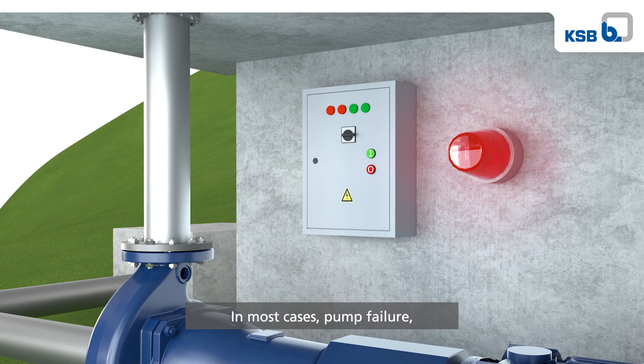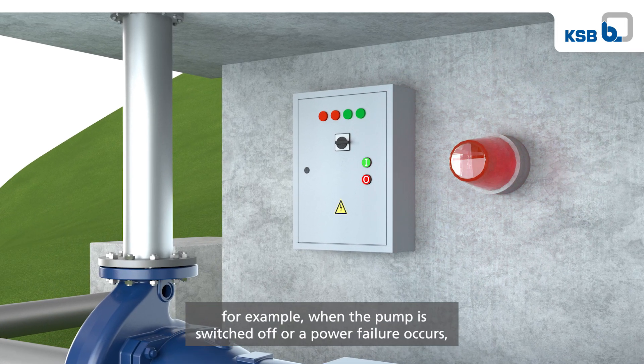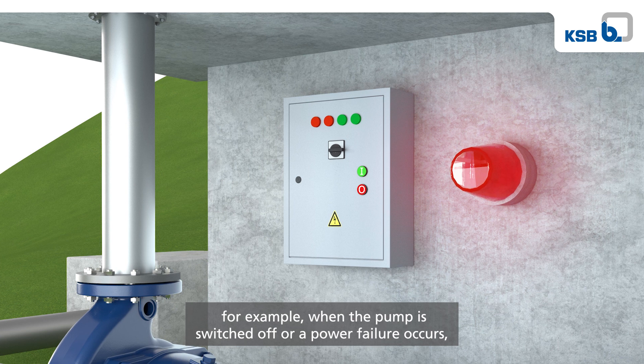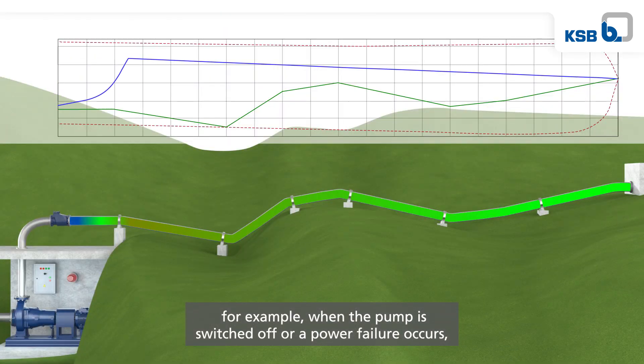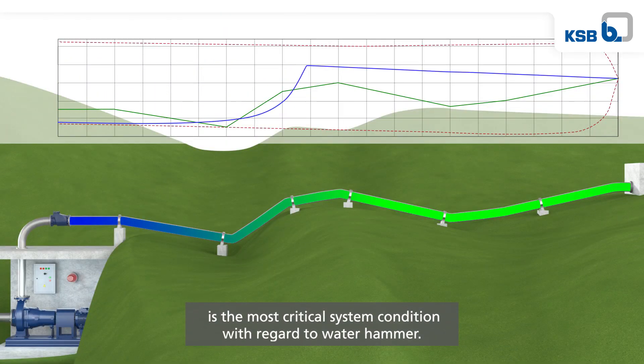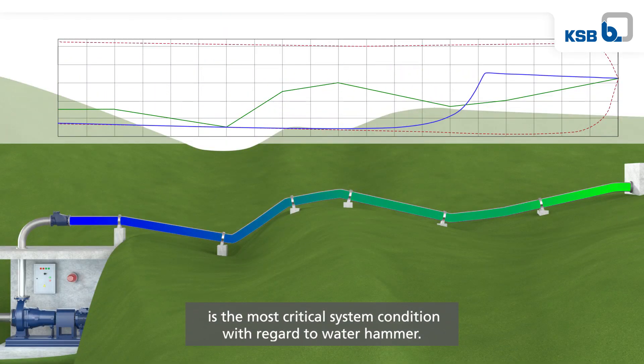The red lines are the envelope curves and represent the maximum and minimum pressures occurring over the entire period. In most cases, pump failure — for example when the pump is switched off or a power failure occurs — is the most critical system condition with regard to water hammer.